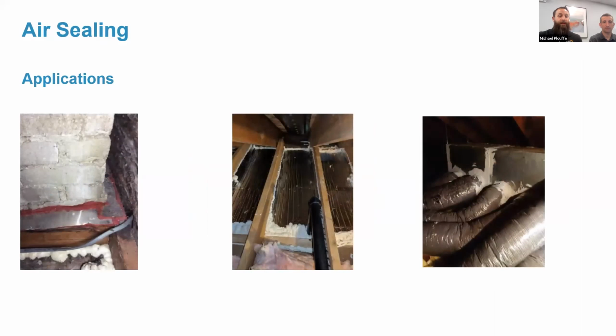Some additional applications around brick chimneys are a major area of air loss in a building. Not super common in the commercial sector, more of a residential, but some of the smaller commercial buildings, that will definitely be a concern. And on the right is a good example of the duct insulation being performed with a mastic material at all those joints where the branches connect to the main manifold for the ventilation air. You want to make sure there's no air leaking there, and that it's all getting to the intended space.